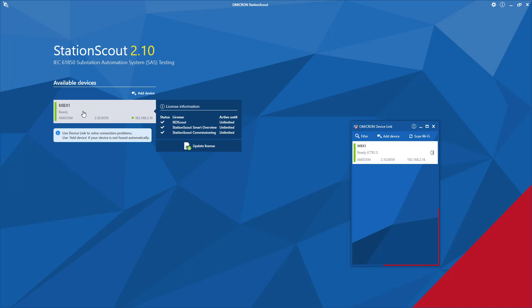We basically need to connect the StationScout software-installed PC to the control port of the MBX1 — either directly or via Ethernet fiber in between. In case you find a different color code instead of green, you can always use the Omicron Device Link software application, which installs together with the latest version of StationScout. You can launch Omicron Device Link from the Start menu or from the StationScout home screen, where you can manage the IP address of the control port.